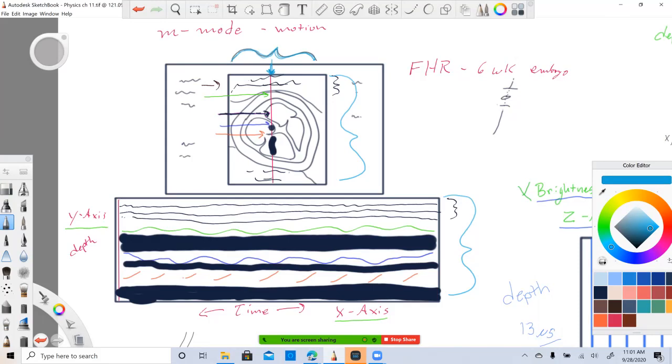So basically the machine is alternating between taking the entire grayscale picture and then doing one pulse in that one little line. And then it takes the whole picture and pulse, the whole picture and pulse. So it is kind of doubling up the amount of grayscale imaging on that one spot, but it's still grayscale. So the energy along that line does increase, but it's pretty negligible. But it does increase, in case there's ever a question on that.